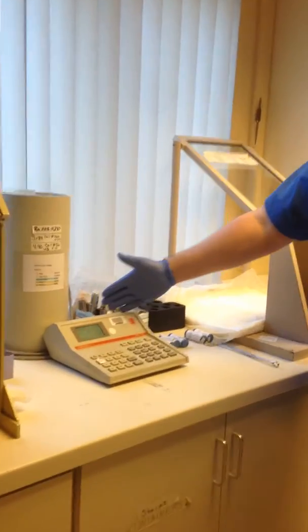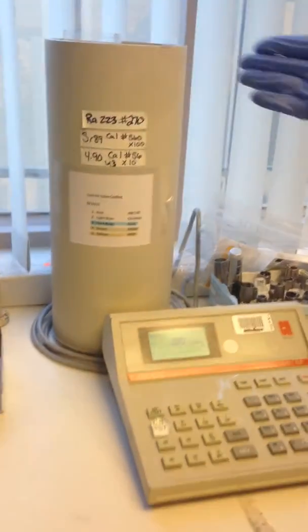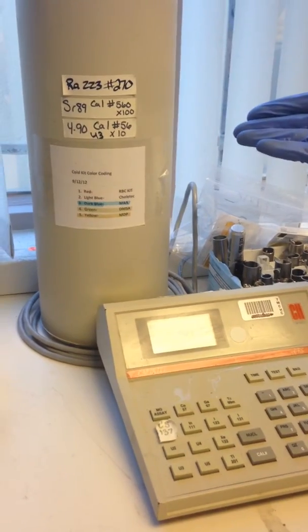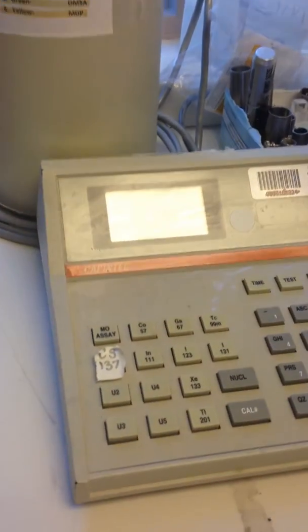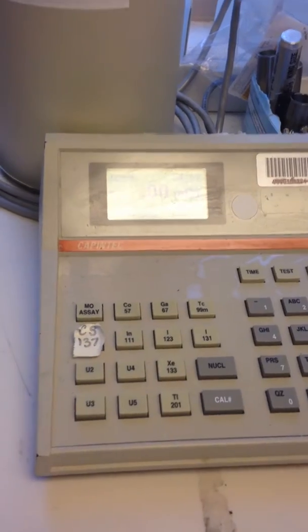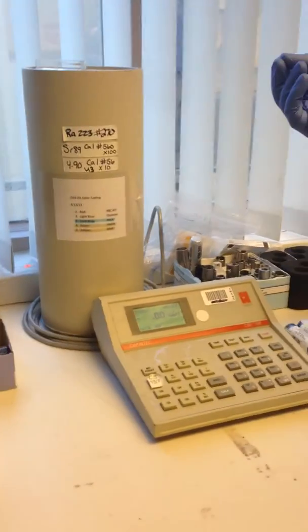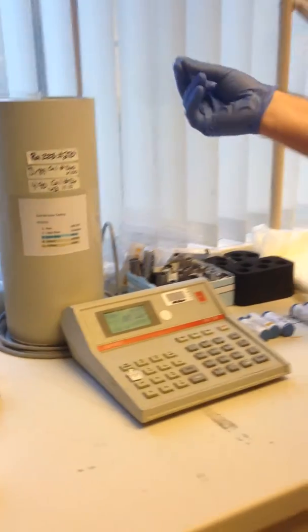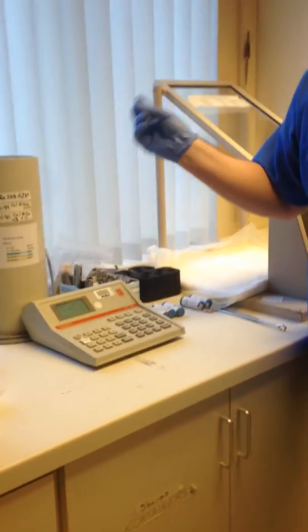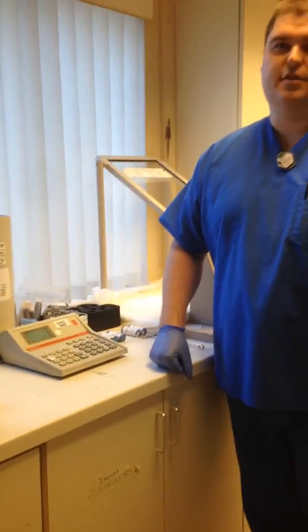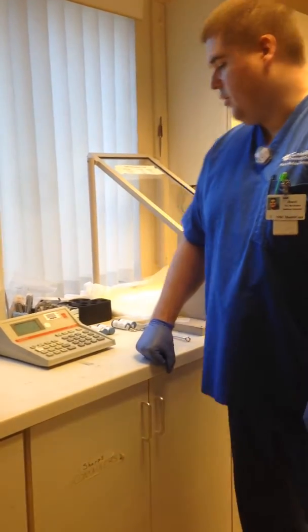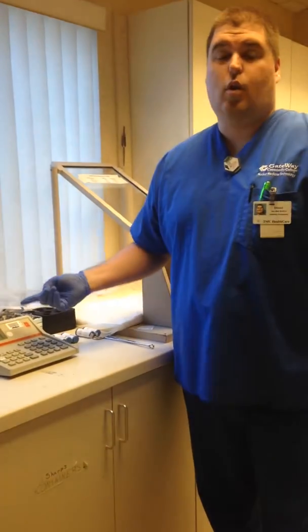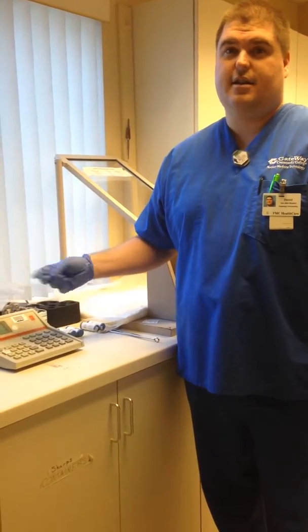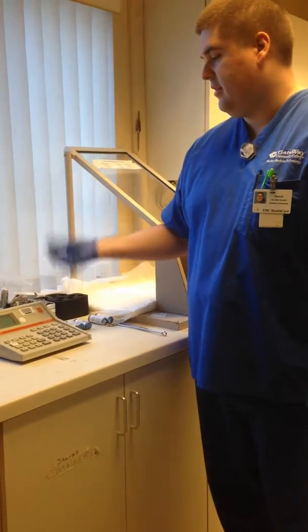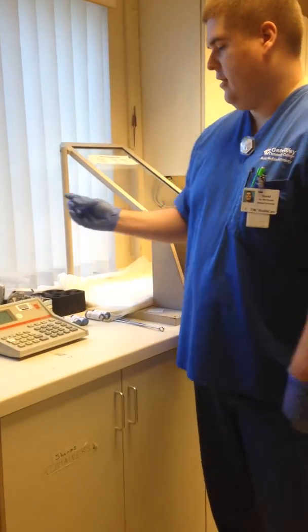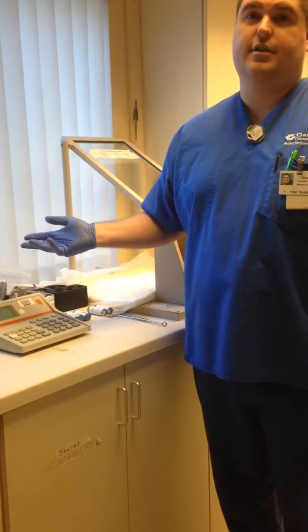Right here is our dose calibrator. And this is a very important piece of equipment that we use every day. What it does is make sure that when we're measuring doses for patients throughout the day, we're getting an accurate measurement, so we know that we're giving the right amount of radioactivity to our patients. So we want to do this quality control daily, and it's very important that we do that so that we can provide good patient care. And so I'm just going to show you how to do that quality control.